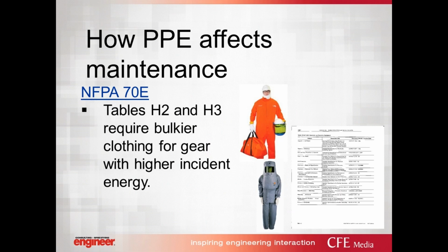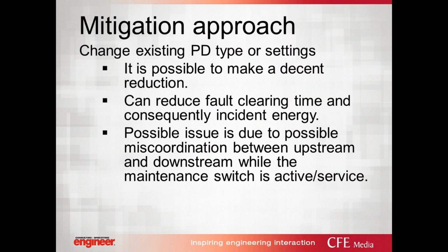When you are donned with full PPE, in a hood, coveralls, or coat and pants, any activity that you take on takes a much longer period of time to complete. Again, the NFPA 70E charts will almost always err toward higher levels if an arc flash study has not been completed. So there is a long-lasting effect of not having an arc flash study. With that, I'll turn it over to Zia to get us into our mitigation techniques.